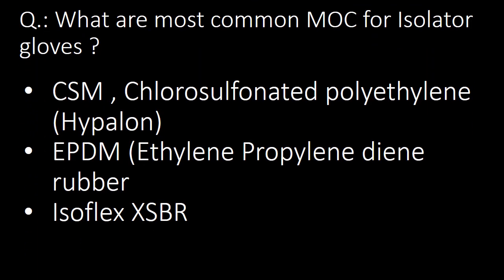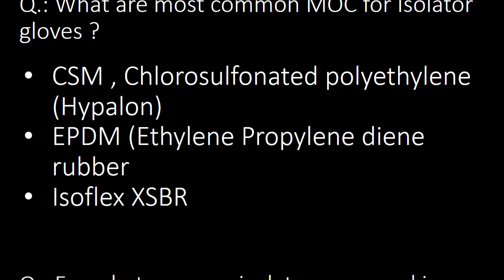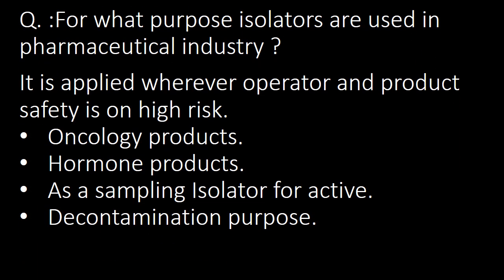The next important question: what are the most common materials of construction (MOC) for isolator gloves? Hypalon, neoprene, and Isoflex are the most common MOCs for isolator gloves.